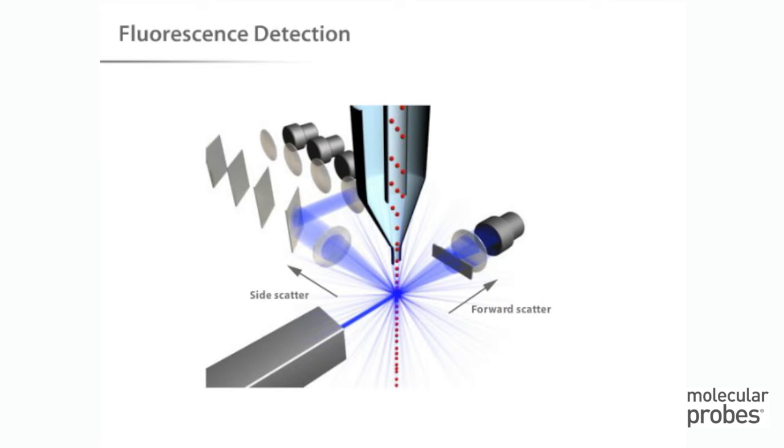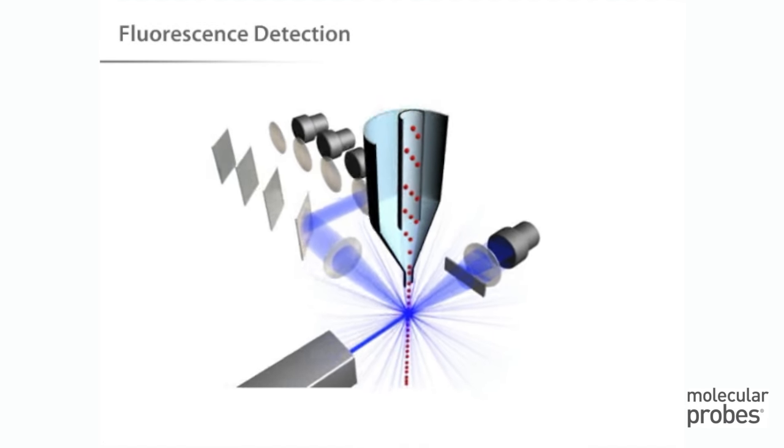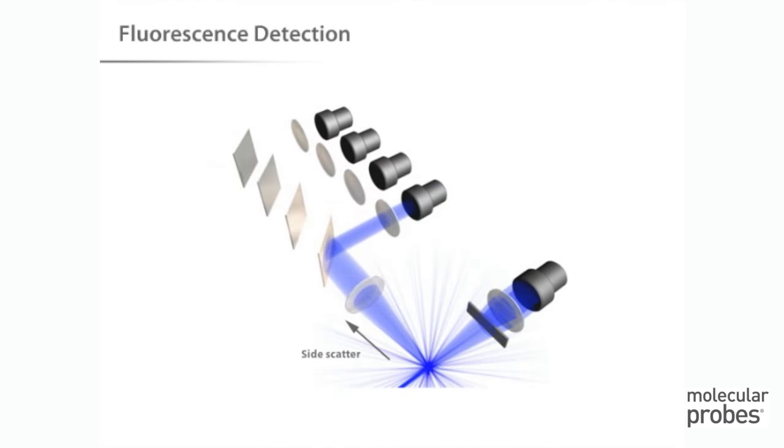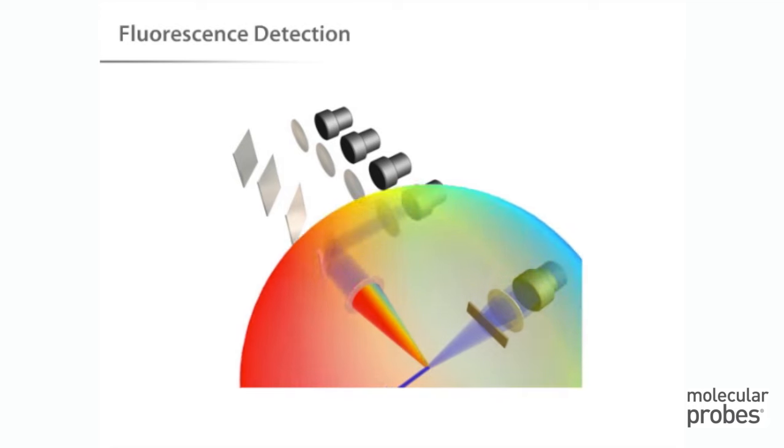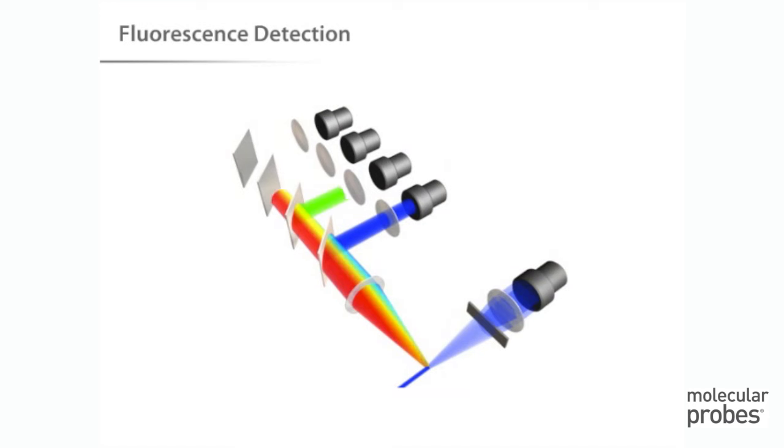How is this fluorescence information collected? The fluorescent light, coming from labeled cells as they pass through the laser, travels along the same path as the side-scatter signal. As the light travels along this path, it is directed through a series of filters and mirrors so that particular wavelength ranges are delivered to the appropriate detectors.